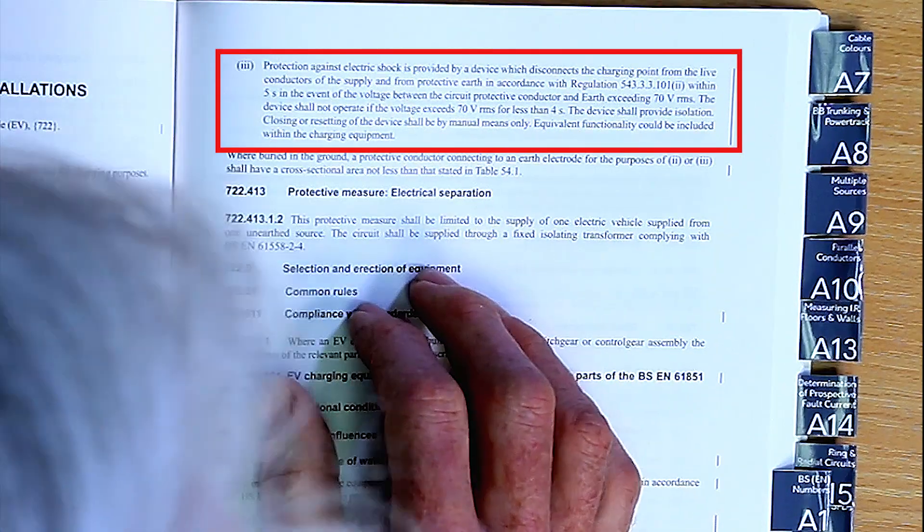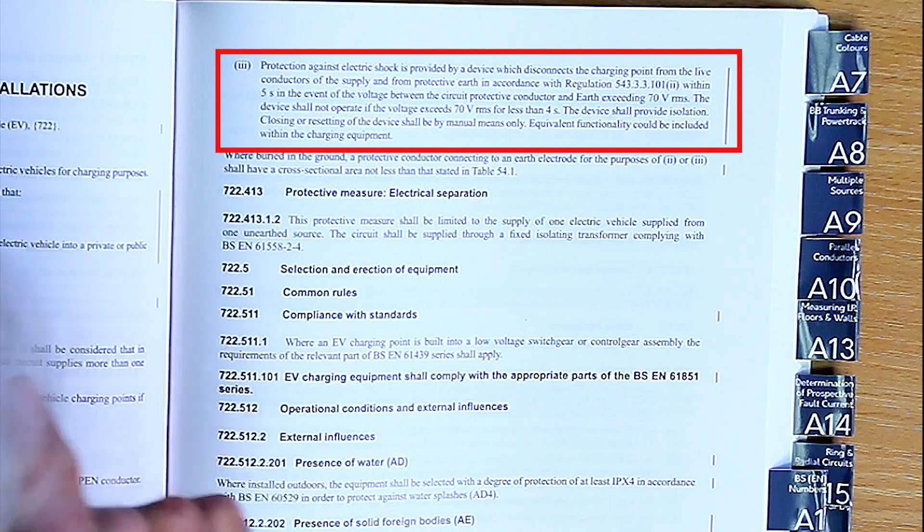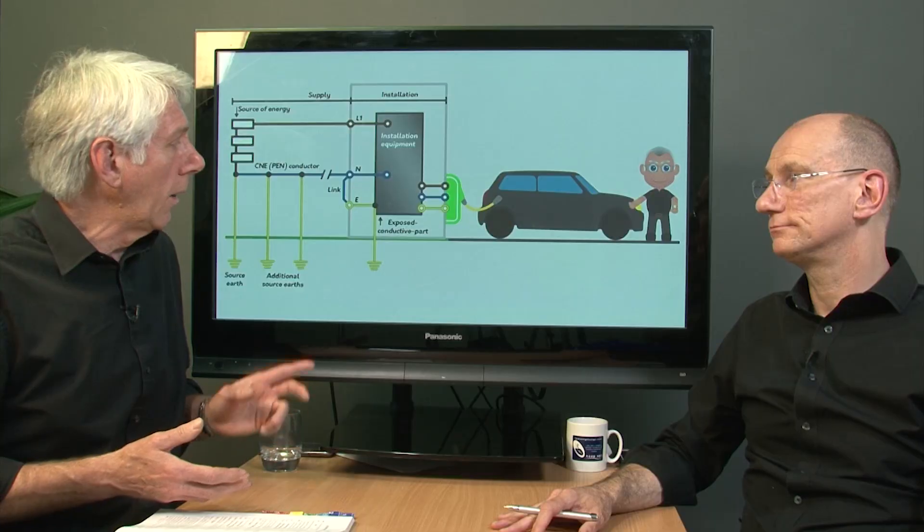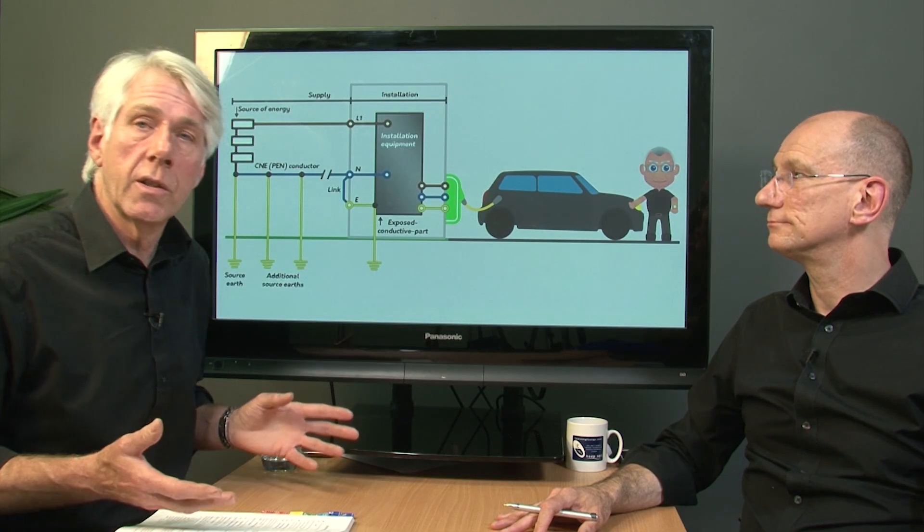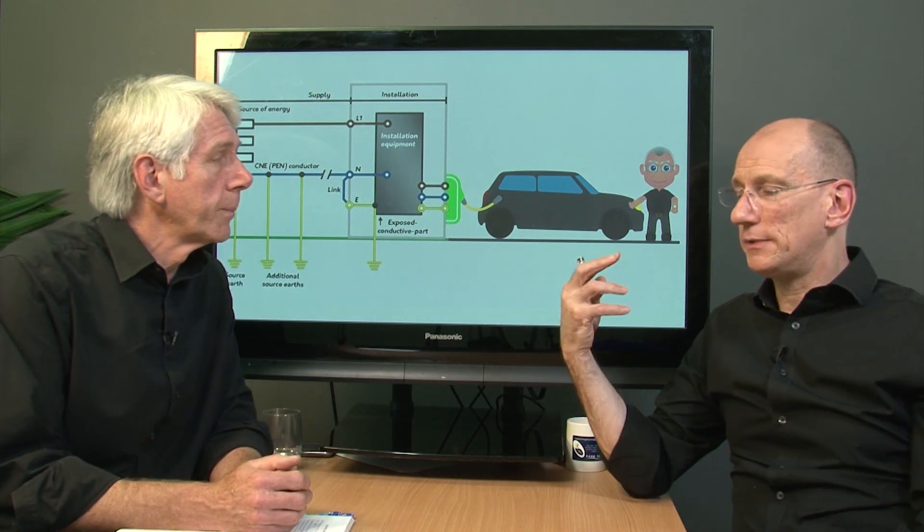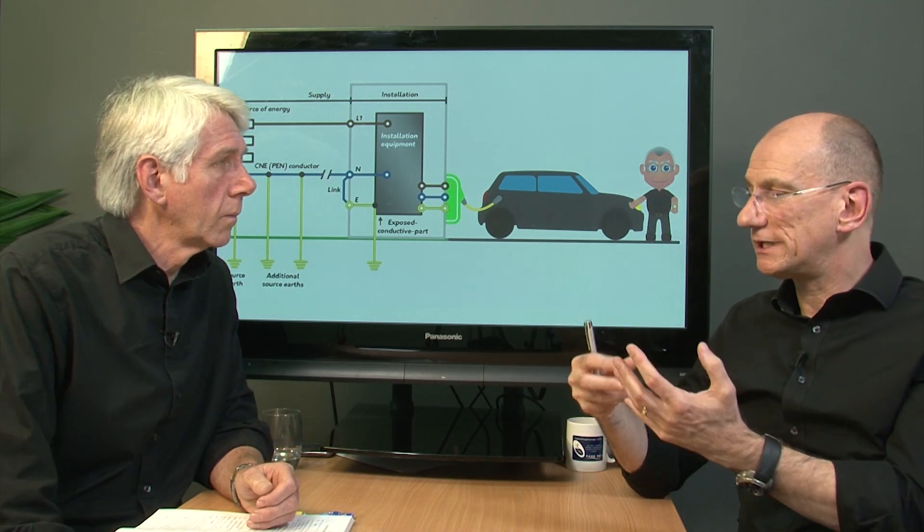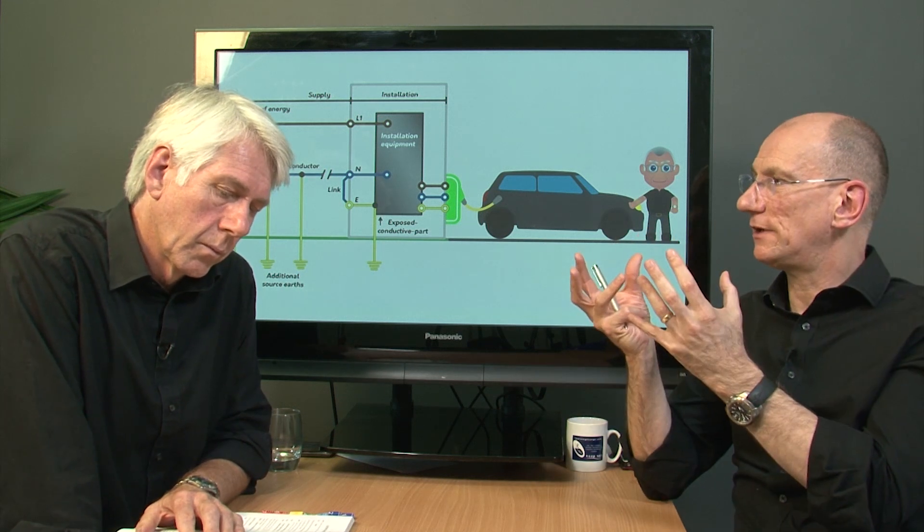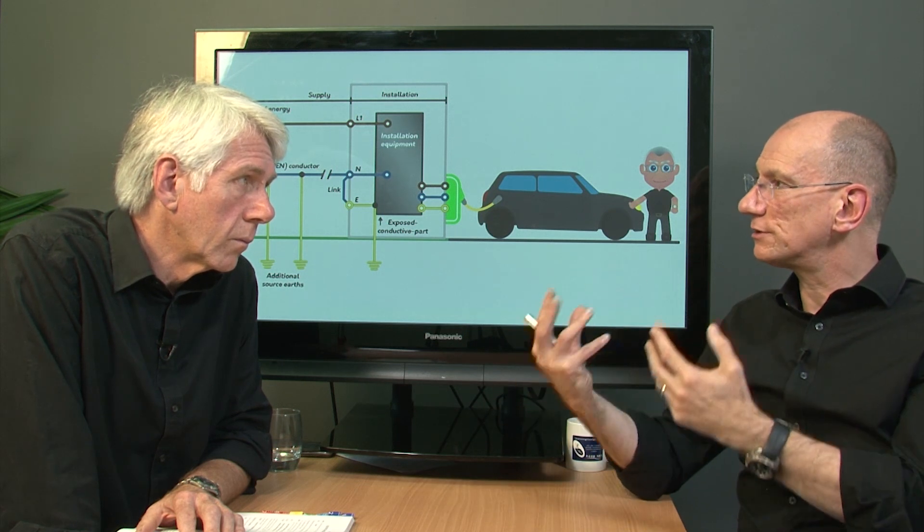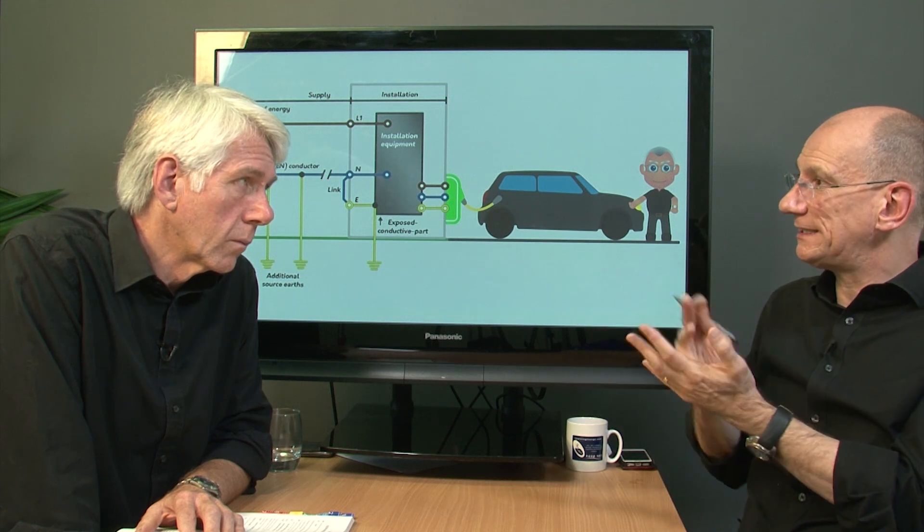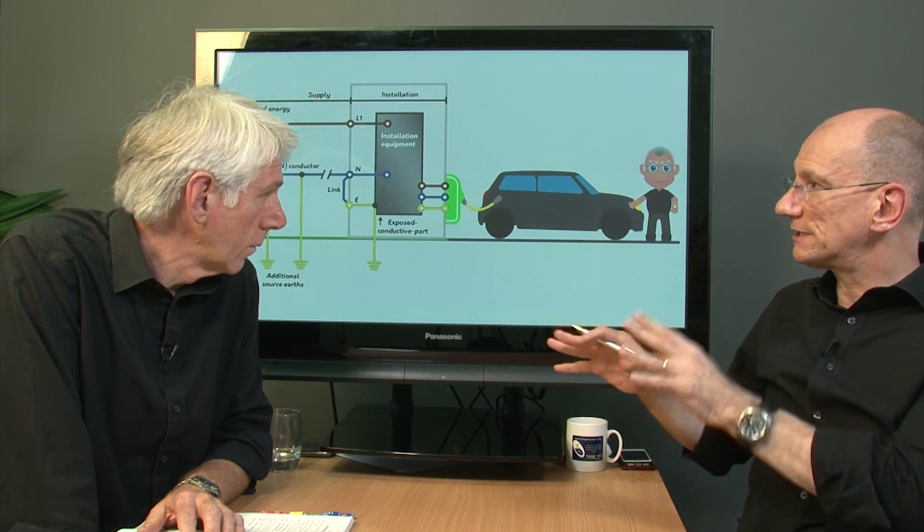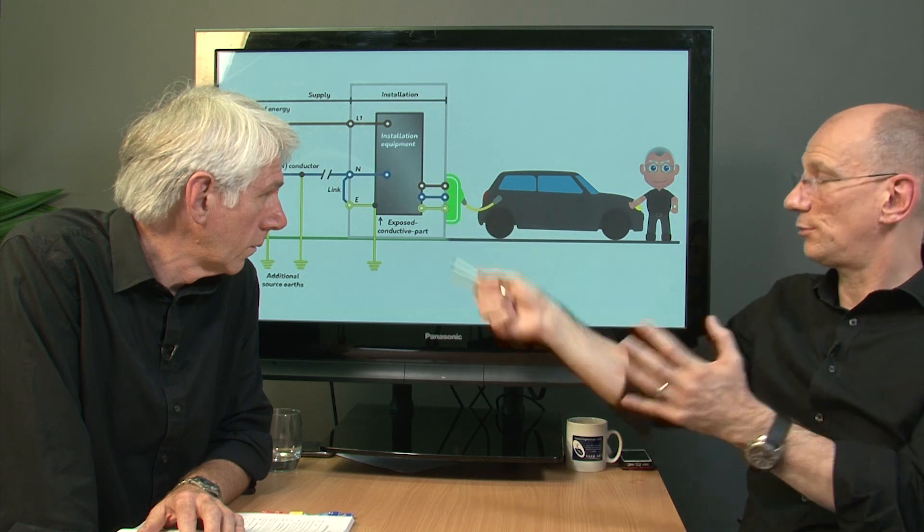Then we have number three. A protection against electric shock is provided by a device which disconnects the charging point from the live conductors of the supply and from protective earth in accordance with regulation 543.3.3. Now, until recently, we were saying no such device exists. But in fact, they are now starting to appear in various forms. Yes. And involved with the charging mechanism itself. Yeah, it could be. I mean, there's a little bit more detail in there that we could just tease out. This particular device that they're talking about never existed in the 17th edition. It was looking to monitor the neutral. And even if you had an RCD and it tripped, the protective conductor is still in contact with the outside metalwork. So even if it disconnected the line of neutral and there was a rise in the potential there, it would probably still export out. So it needs to disconnect the protective conductor at the same time.